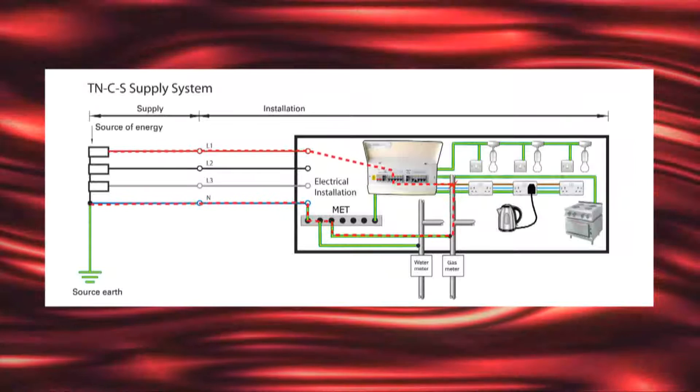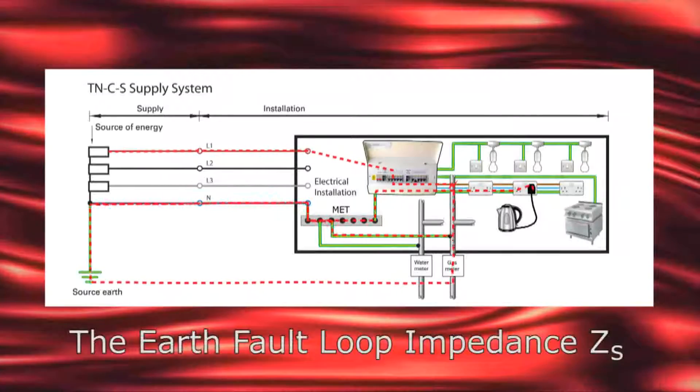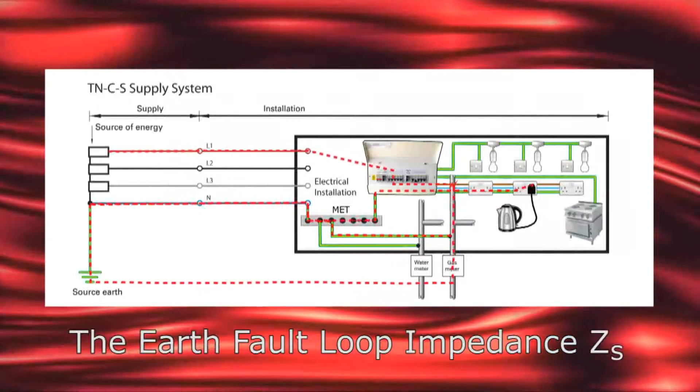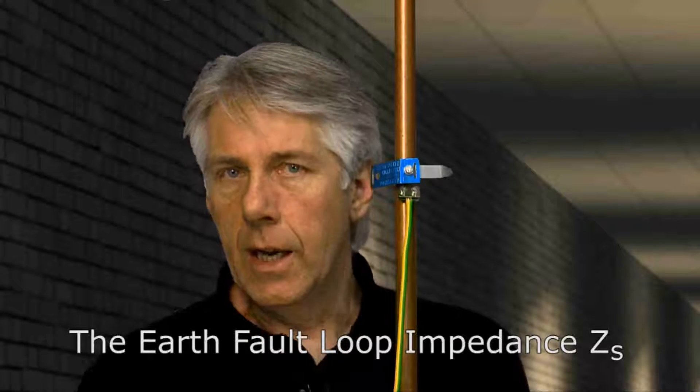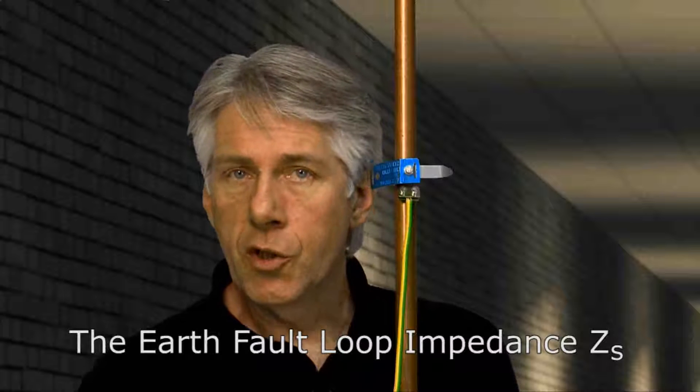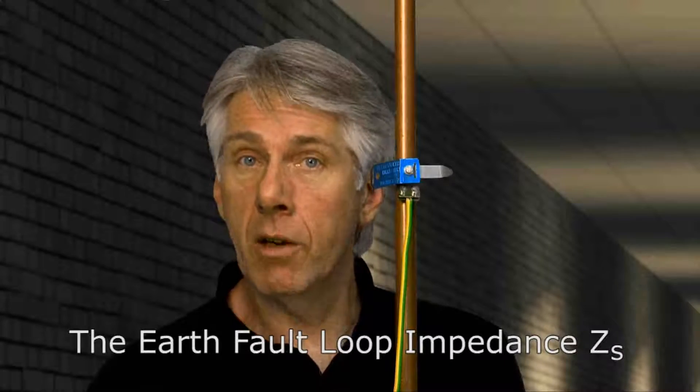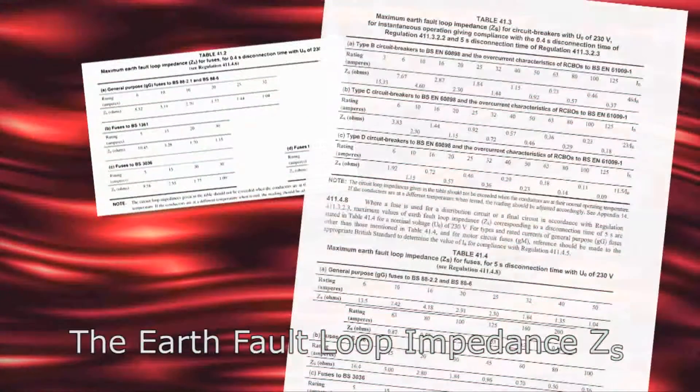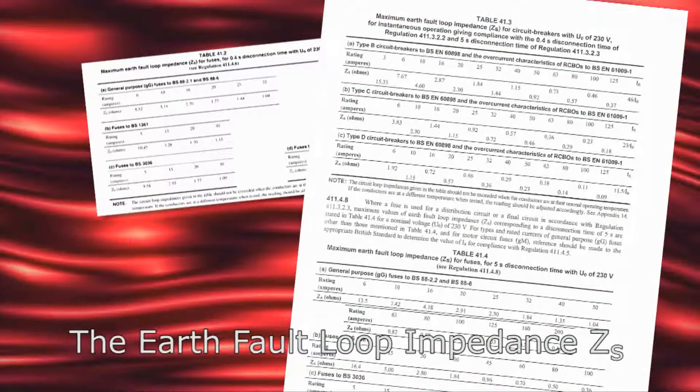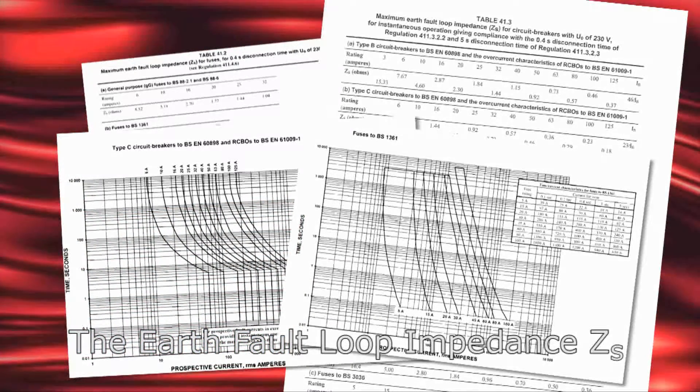The path that earth fault current takes back to the source of supply, whether through pipework and protective conductors or even the earth itself, is known as the earth fault loop, and its impedance ZS is measured in ohms. So when electrical installations are designed, it's important to keep the value of ZS low enough to ensure that sufficient current flows, thus causing the circuit protective device to operate within the required disconnection time. There are tables in the regulations which list maximum ZS values for different types of circuit protective devices, and these have been determined from the time-current characteristics graphs in Appendix 3 of the regs. We'll look at these in detail in other videos in this series.